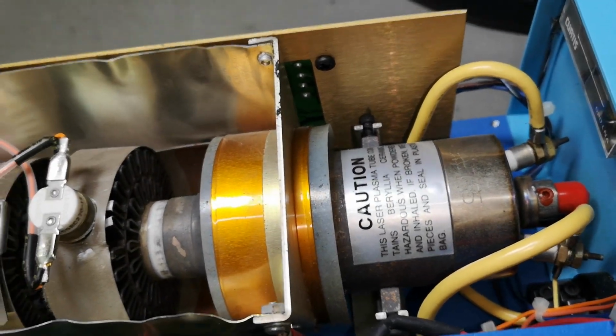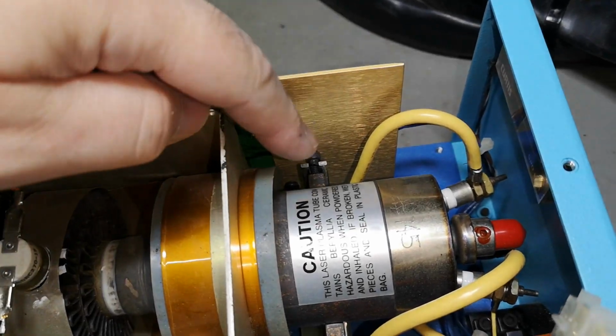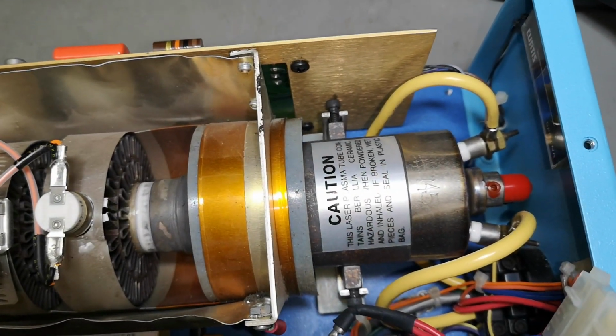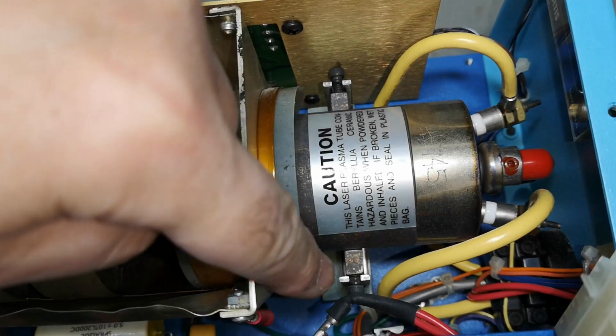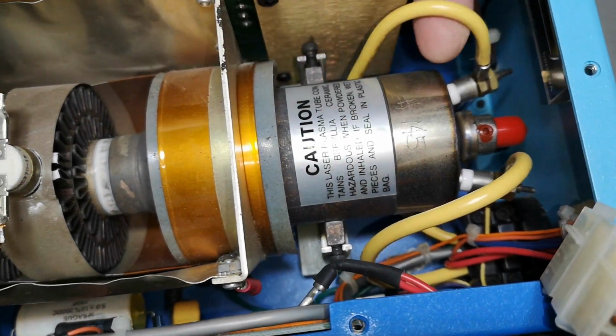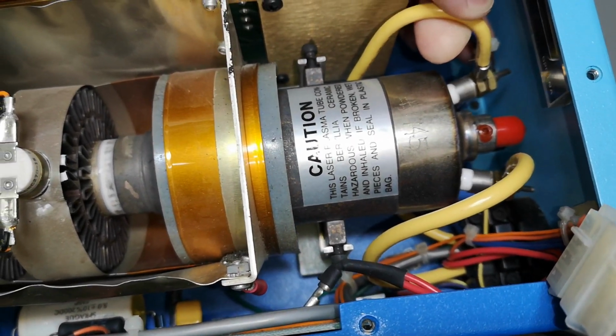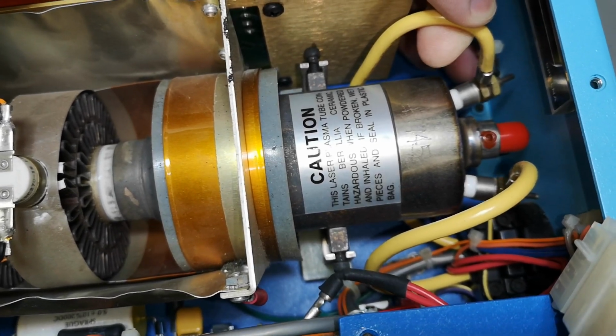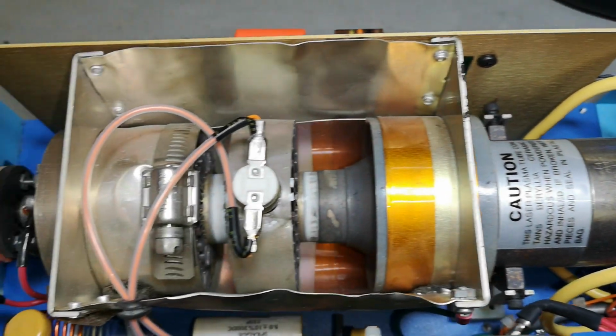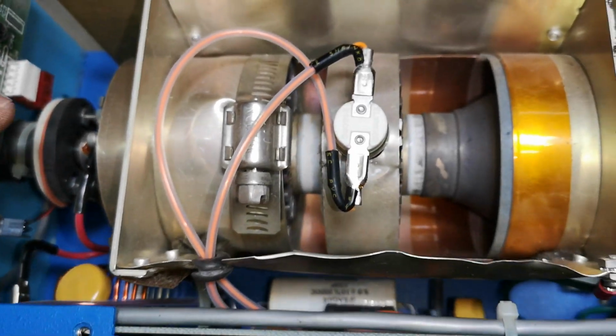There's another problem I can see here, a mechanical problem. Those 2 screws here that hold the tube are actually halfway out, as you can see. That means I can lift the tube freely, and that is not good because it's mounted here in the anode.